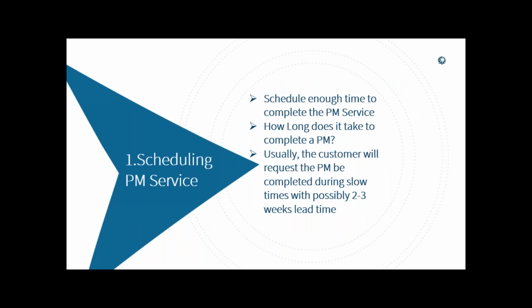Let's look at these. Number one, scheduling PM service. You just can't walk up to the CT and say, I'm here to do your PM on your injector. It can take 2 to 3 weeks to schedule that. And they're going to want it done after hours or in the slowest time. So schedule enough time to complete the PM service. How long does it take to do a PM on an injector? Average time, about 2 hours. About 2.5 maybe if it's dirty. And usually the customer will request PM completed during slow times with possibly a 2 to 3 week lead time. Why do they need a 2 to 3 week lead time?